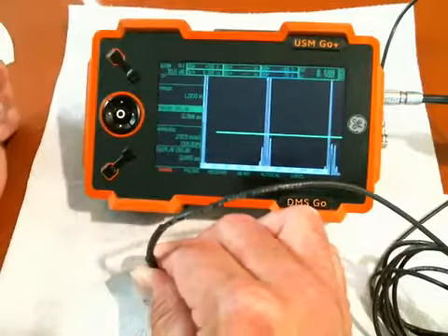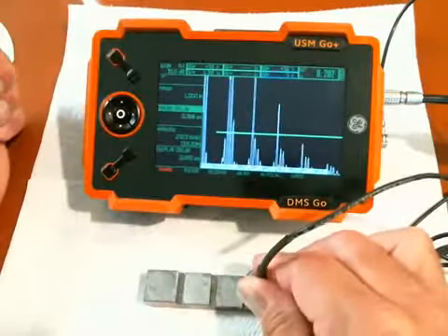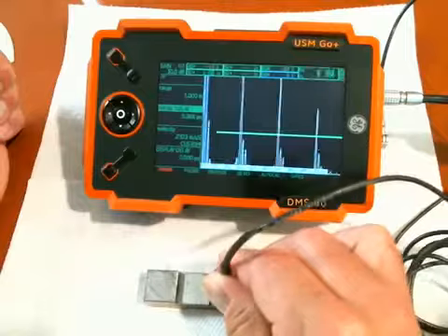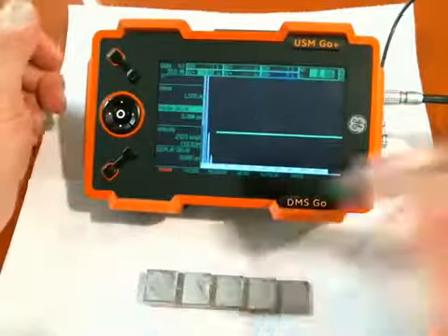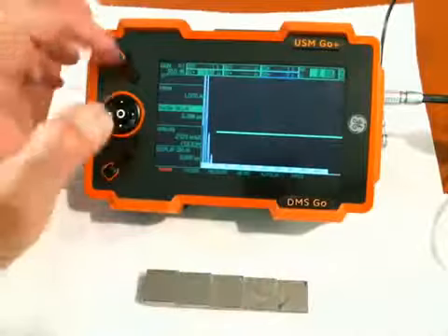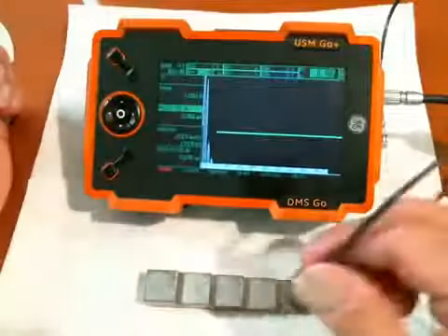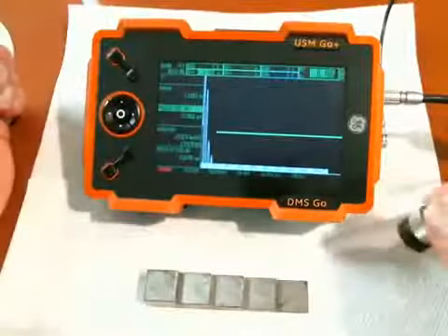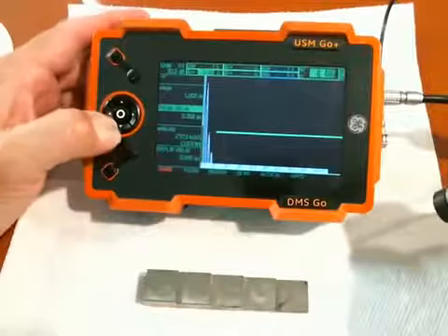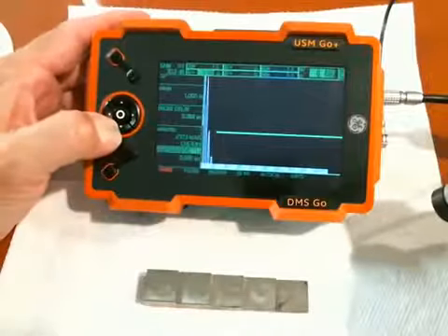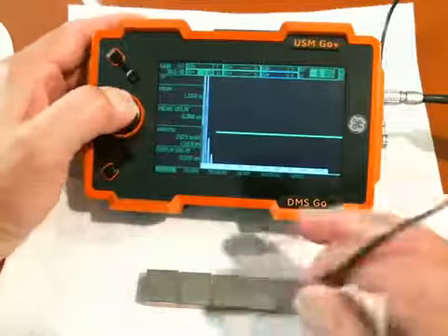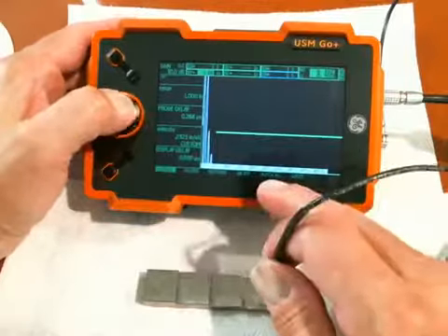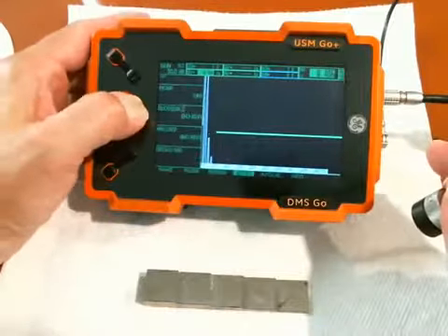Okay, get our 1/2 inch, 0.2, 0.3, 0.4. Now, the process of adjusting probe delay and velocity till we get calibrated on 2 thickness points, that's a little bit inconvenient, and it can also be a time-consuming thing to do. So we've provided an AutoCal feature. If you look, there's an AutoCal menu.